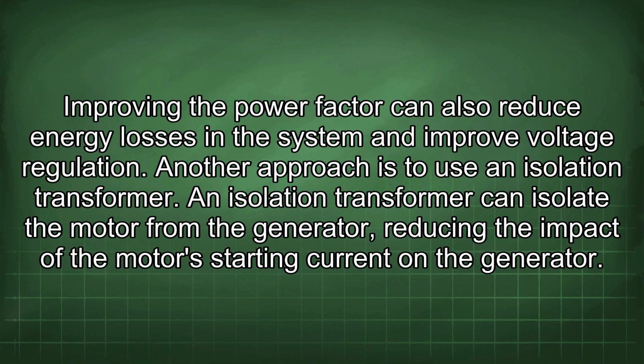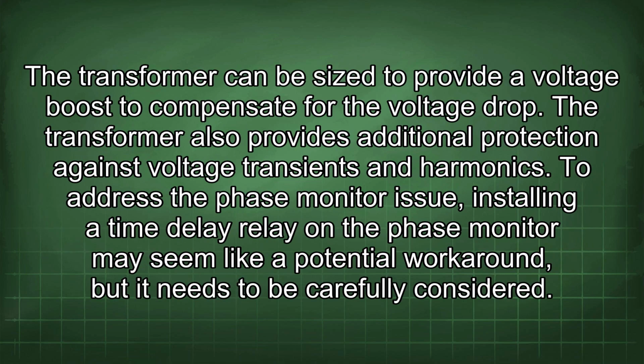Another approach is to use an isolation transformer. An isolation transformer can isolate the motor from the generator, reducing the impact of the motor's starting current on the generator. The transformer can be sized to provide a voltage boost to compensate for the voltage drop. The transformer also provides additional protection against voltage transients and harmonics.